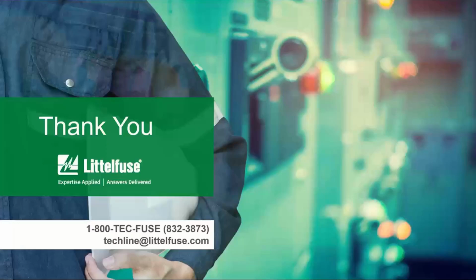And the second question is from Nazarene: what standard for arc flash calculations is used as the basic guideline for complete analysis and calculation in Canada? Well, in Canada, the Canadian Electrical Code and in particular the CSA Z462, that's the Canadian equivalent of the NFPA 70E, they both reference IEEE 1584 as a standard that can be used for a basis. So that's the one that I'm aware of that it references in terms of the arc flash calculations.